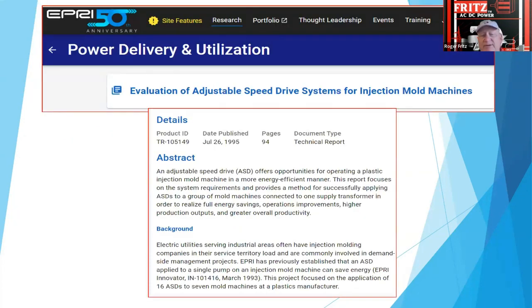I've also been involved with the Electrical Power Research Institute on variable speed drives. So in 1995, there was a huge report written about VFD applications for plastic processing machines, and we had literally installed thousands of those around the country, and some of them even went international, because we were basically working on a fixed volume machine, and we were making variable volume hydraulics through running motor speed control on fixed volume pumps, and it had a great impact back then. They definitely oversized the pumps a lot more than they do today. And even now, the newer machines are all coming out with VFD technology, running on it if they're a hydraulic machine, or they're using VFD technology running all the servo motors that run the mechanical ball screws on machines, instead of using hydraulic pumps.